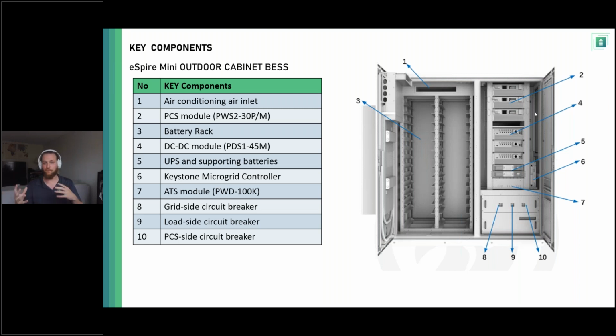Now, we can make recommendations. Say you do need it for a critical application, we would look to pair it with a UPS that is relatively cheap, right? That can handle, say, the first 5 to 10 minutes of that critical outage, just in time for the battery system to switch over and form the grid. But that's typical of these very critical situations. So if you have questions about that, just let us know. But ultimately, that's what we would recommend in that situation.